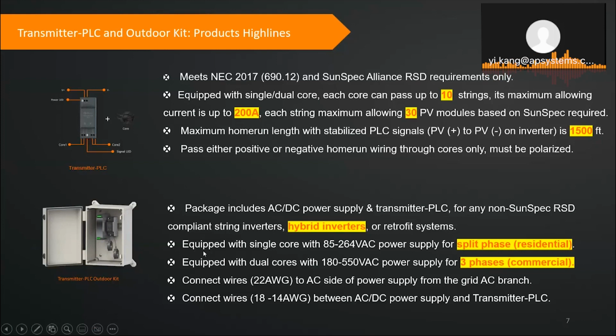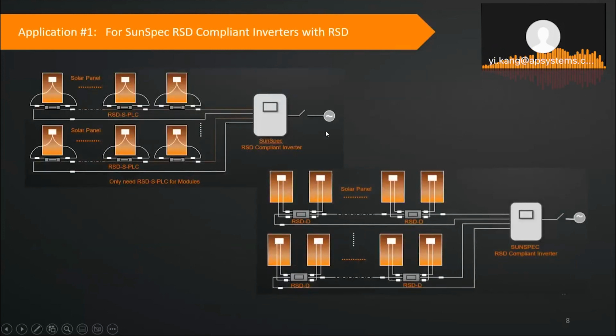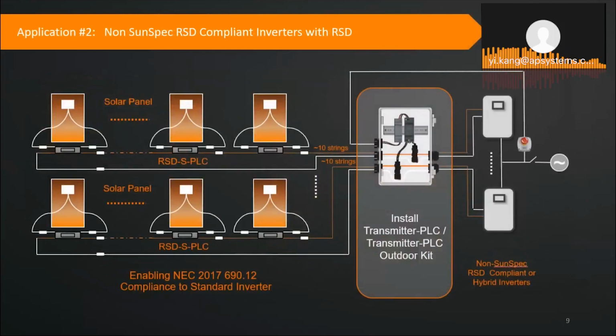Additionally, just one tip here. You see the equipment with a single core with 85 to 264 VAC power supply. It's only for residential and only for a hybrid inverter. So when you purchase this product, pay attention to this, because if you order the wrong AC/DC power supply, it will not work. This is a simple drawing, both for the single and the dual, but we are only focusing on the single. Pretty easy.